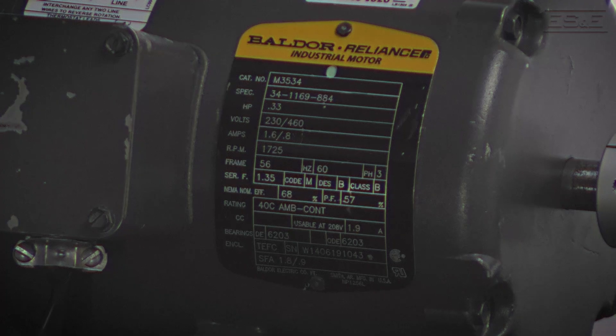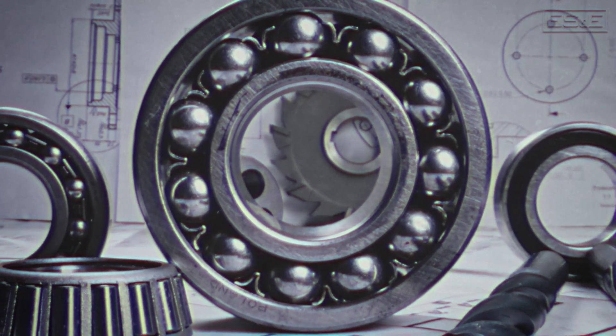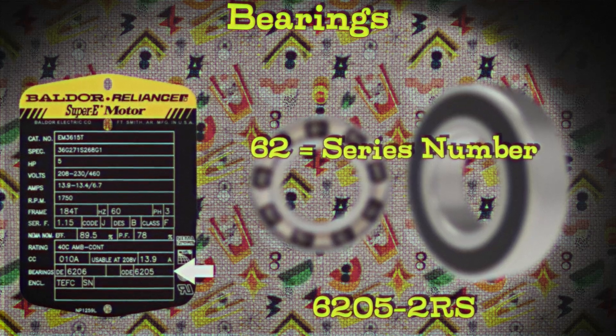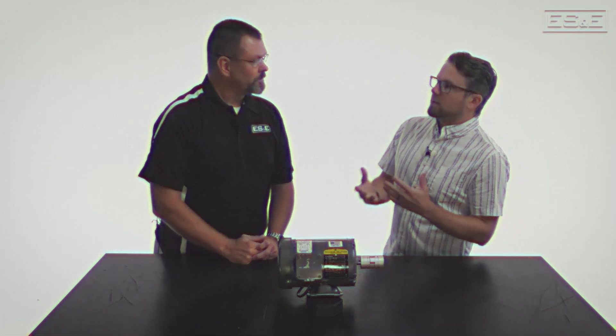Let's go on to something I can actually read — bearings. What are these numbers? The bearing code is a series of letters and numbers describing the specific type and size of the bearings used — the front and back bearings' actual part numbers. If you ever have to replace those bearings, it gives you the actual part number. For example, 6205-2RS: the 62 is the series or type of bearing, 05 is the size — the inner and outer diameter — and 2RS represents two rubber seals on each side. Knowing the bearing code can really help with maintenance and getting back up and running quickly.